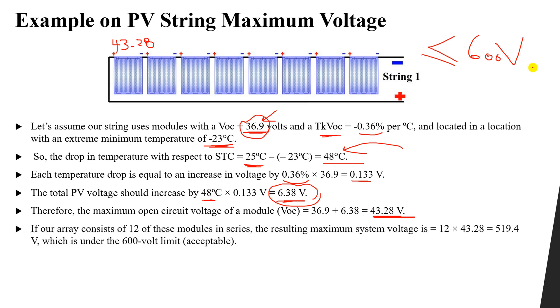If we connect 12 modules in series, the total maximum open-circuit voltage is 12 × 43.28V = 519.4V. Since 519.4V is less than 600V, connecting 12 modules in series is acceptable — it produces less than 600V even at the extreme minimum temperature.